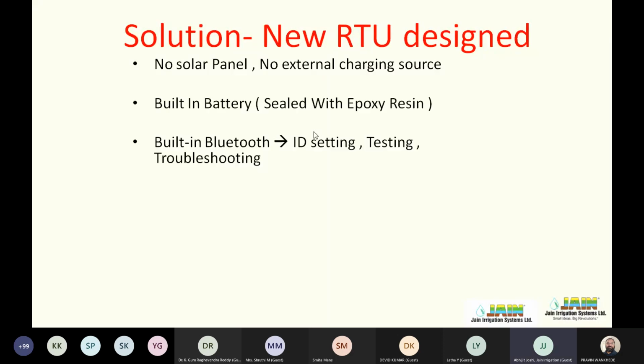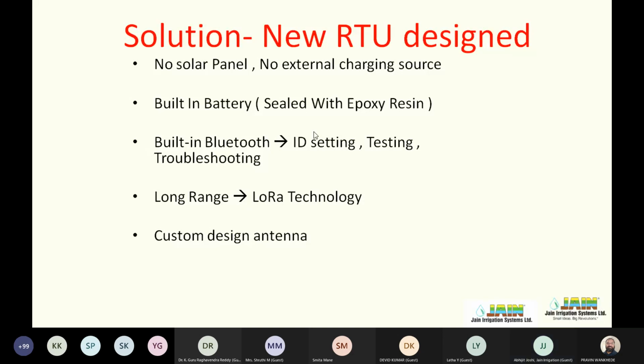So we went for a built-in battery, non-rechargeable battery operated RTUs, in which the battery life shall be a minimum of 5 years. We designed the battery accordingly, and this was actually only for cases where you need to operate digital outputs, because digital outputs are latching type outputs and do not require much power. So the maximum power requirement is only for communication, and we tried to restrict the communication as well.